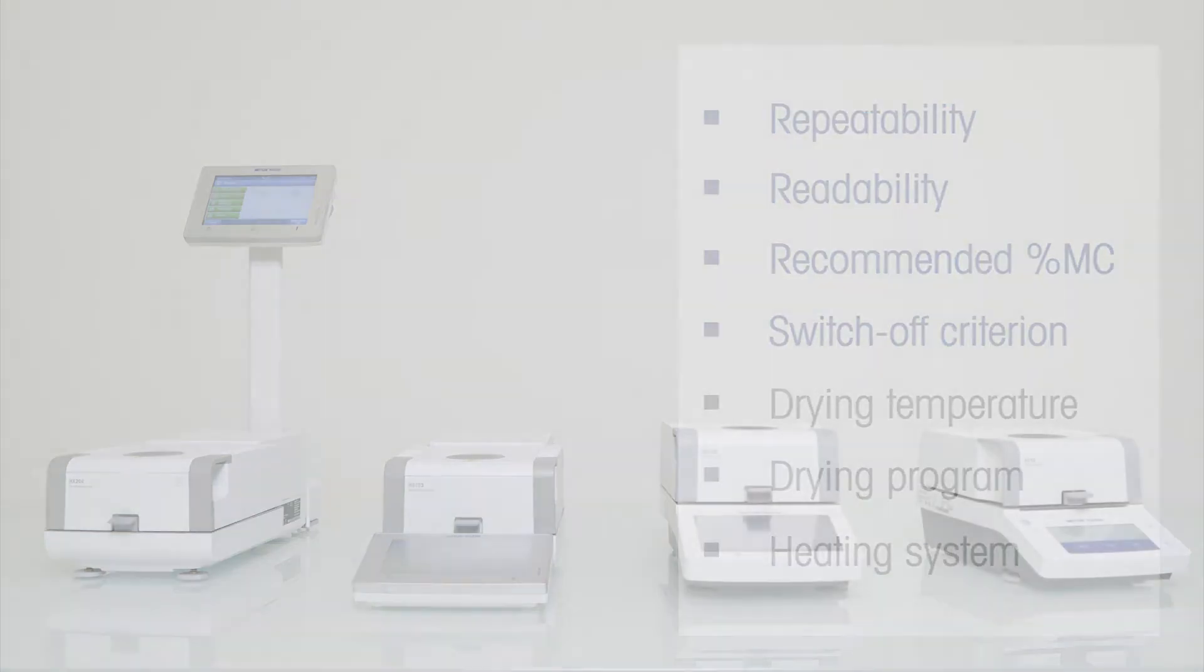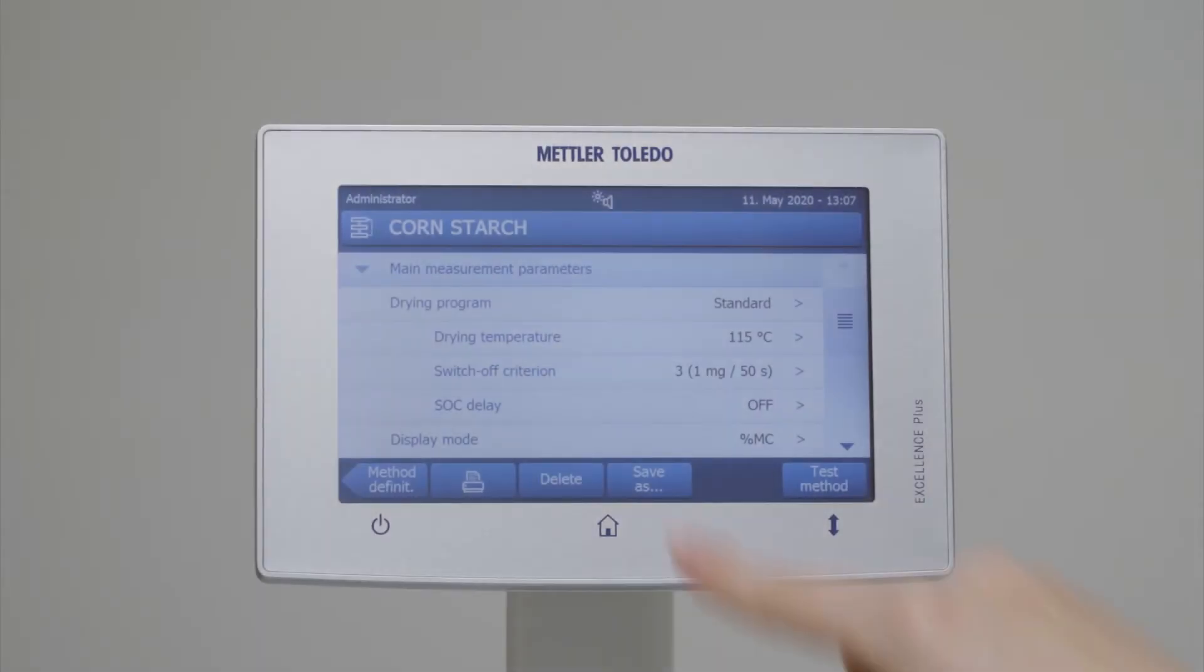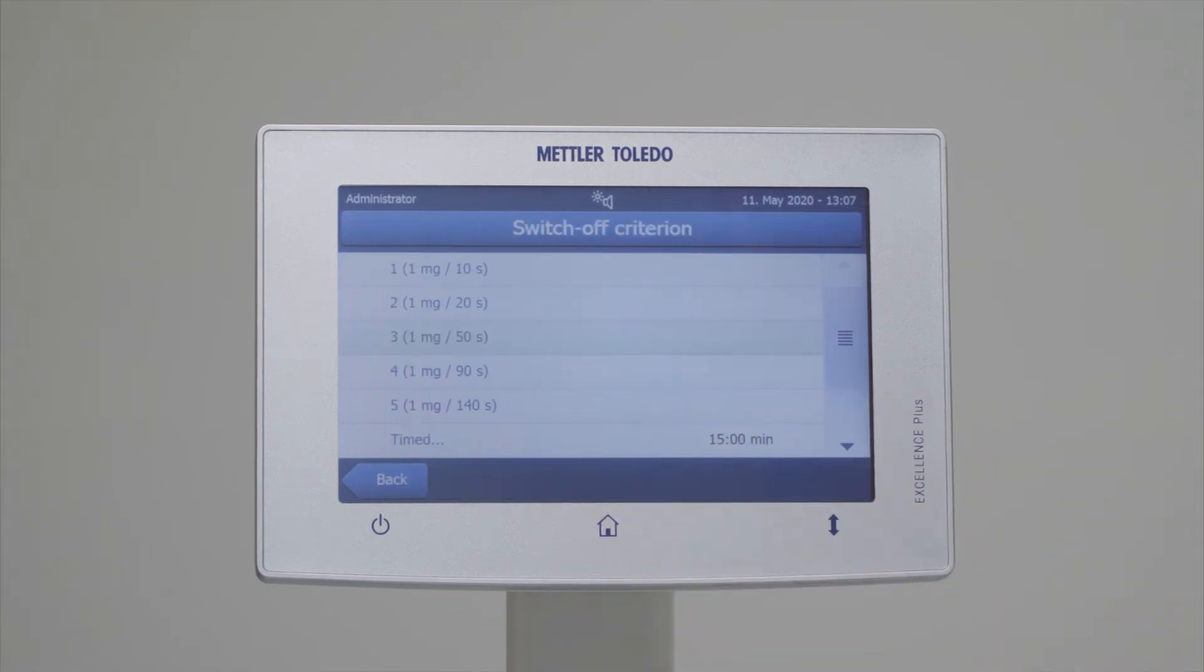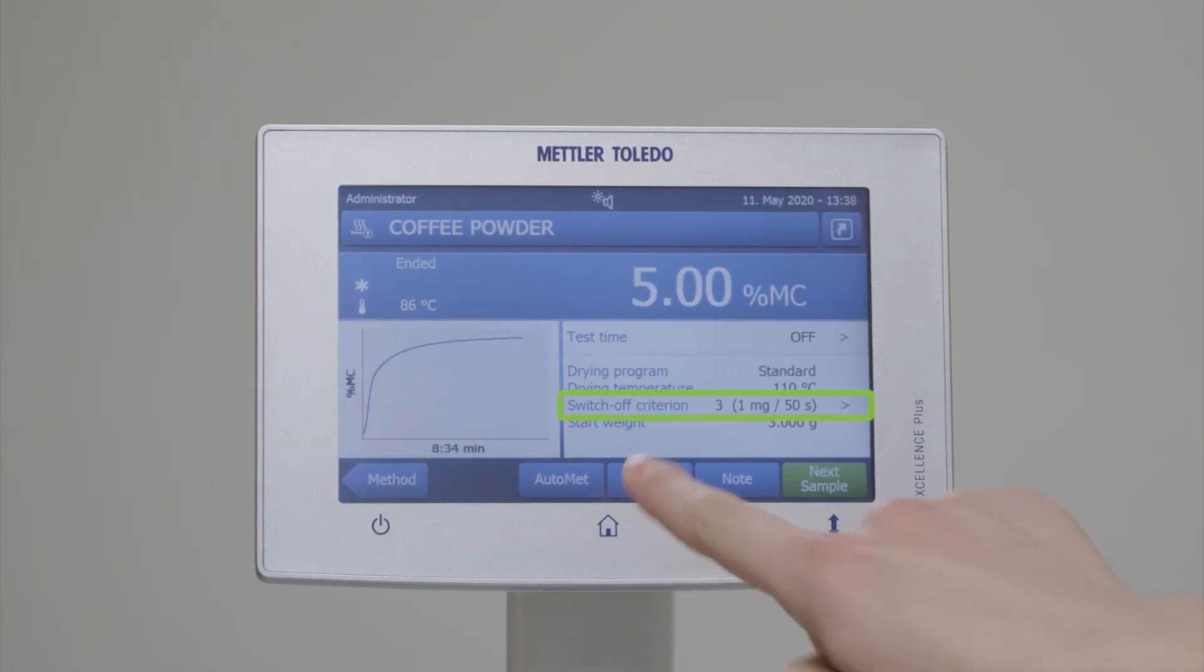The switch-off criterion defines when the measurement ends. There are mainly two options to switch off the measurement. Either you can end the measurement after a certain time, or you consider the weight loss per time. For example, you could stop the measurement when the average weight loss is less than 1mg over the past 50 seconds.